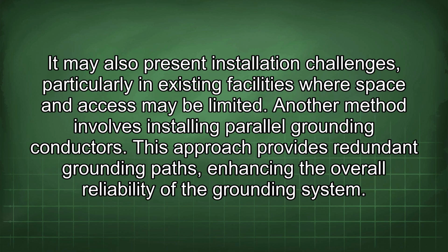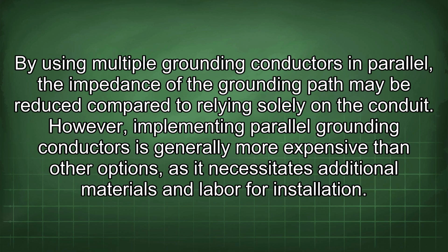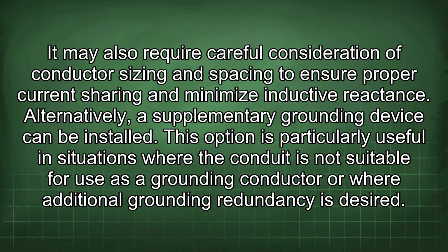Another method involves installing parallel grounding conductors. This approach provides redundant grounding paths, enhancing the overall reliability of the grounding system. By using multiple grounding conductors in parallel, the impedance of the grounding path may be reduced compared to relying solely on the conduit. However, implementing parallel grounding conductors is generally more expensive than other options, as it necessitates additional materials and labor for installation. It may also require careful consideration of conductor sizing and spacing to ensure proper current sharing and minimize inductive reactance.